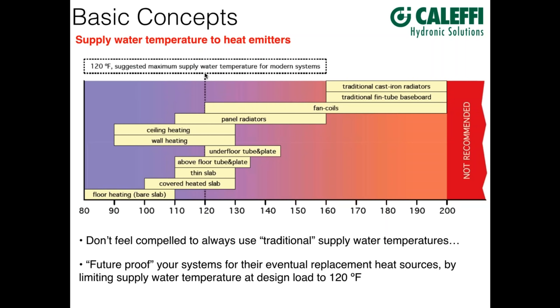Don't always feel compelled to use traditional water supply temperatures. Fin tube baseboard can actually operate at temperatures below 160°F. You can operate fin tube at 100°F — the output will be low, but in a situation with low heat loss from the space and ample wall space, it would heat the space. It's not traditional practice, and you will need a lot of wall space when designing fin tube around 100°F supply water temperatures. Keep your mind open to the possibilities; don't feel constrained to always go with traditional temperatures.